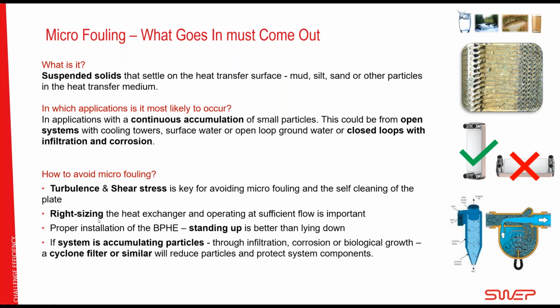Right sizing the heat exchanger will also be a separate slide. Something I will mention just here is proper installation. A heat exchanger that is standing up like this will have less precipitation of fluids than a lying down one, because in a lying down heat exchanger there is more horizontal surface that will allow the particles to accumulate. Think of it as a desk. A desk will accumulate a lot of dust because it's a big horizontal surface, and if you put it up against the wall, there will be less dust on the desk, because there is no gravity pulling the dust to the desk. Okay, that was maybe not the best allegory.